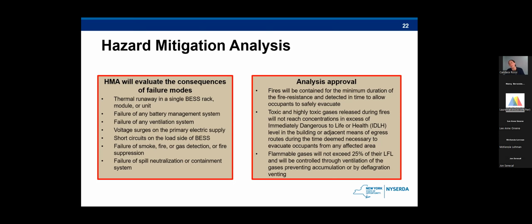And then the local fire code official may approve this analysis, provided that the consequences demonstrate that fires will be contained for the minimum duration of the fire resistance and detected in time to allow occupants to safely evacuate. It could also be approved if they show that toxic and highly toxic gases released during fires will not reach concentrations in excess of the immediately dangerous to life or health level in the building or adjacent means of egress routes during the time necessary to evacuate from the area. It also has to show that flammable gases will not exceed 25% of their lower flammability limit and will be controlled through ventilation of the gases, preventing accumulation.